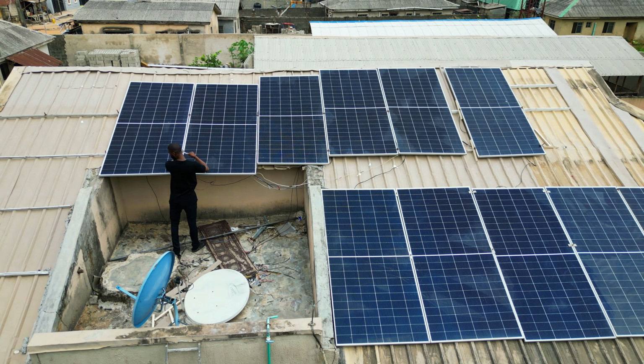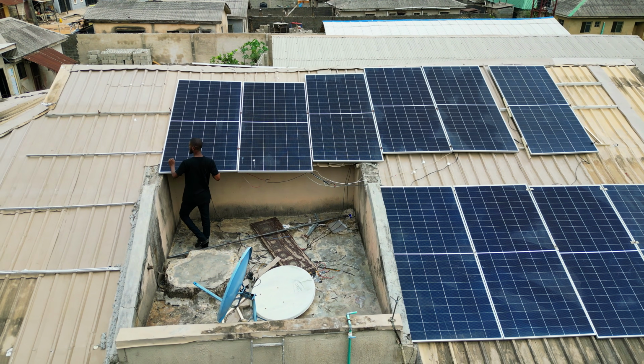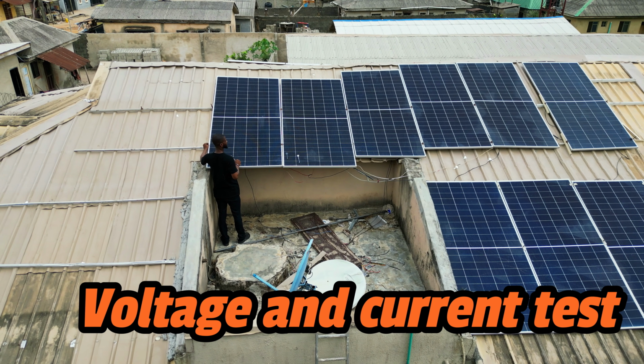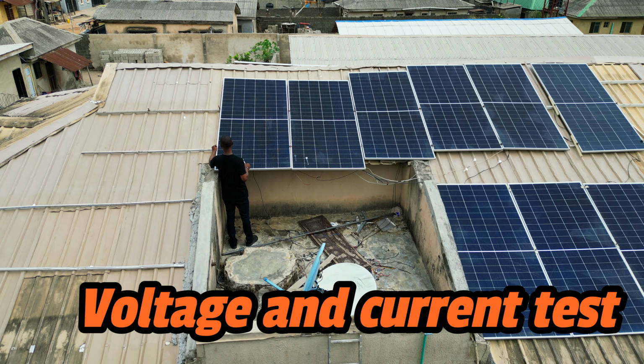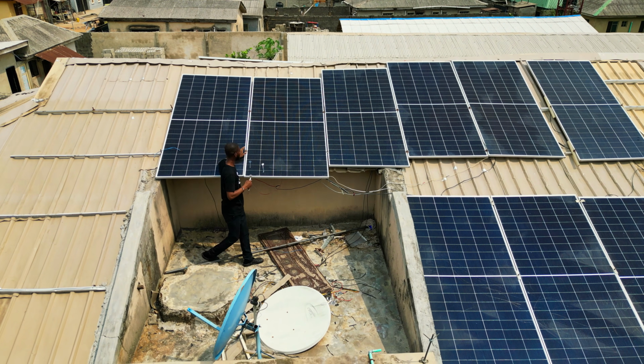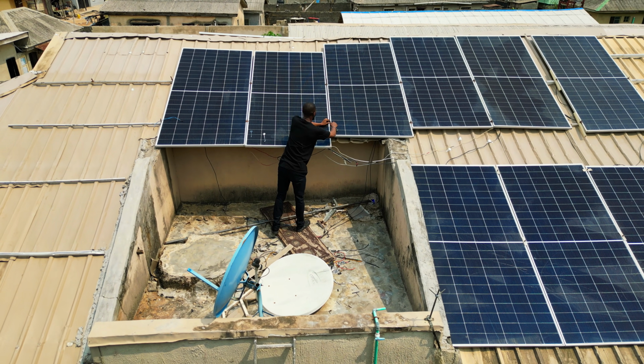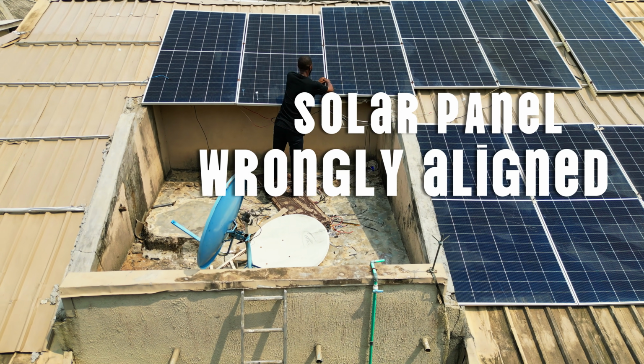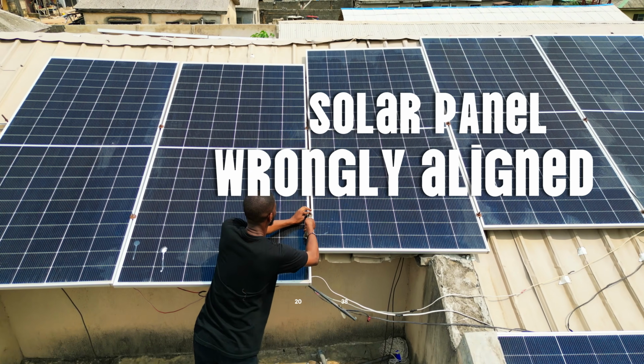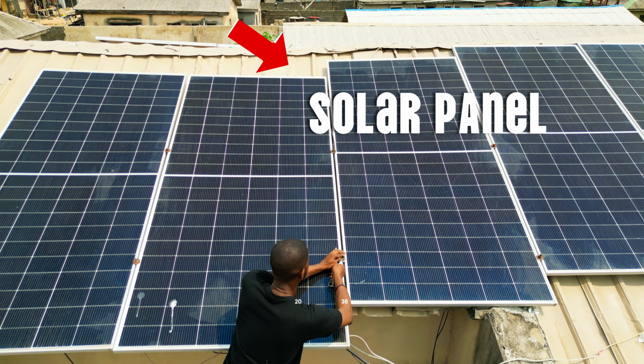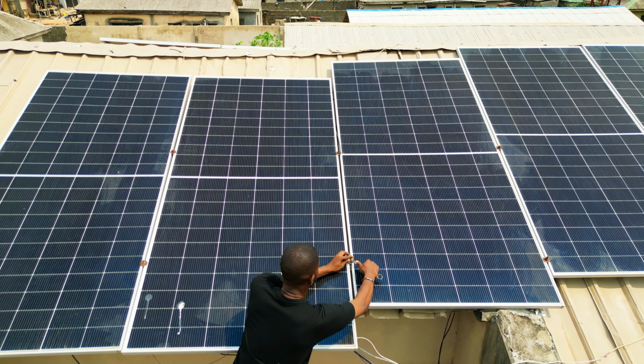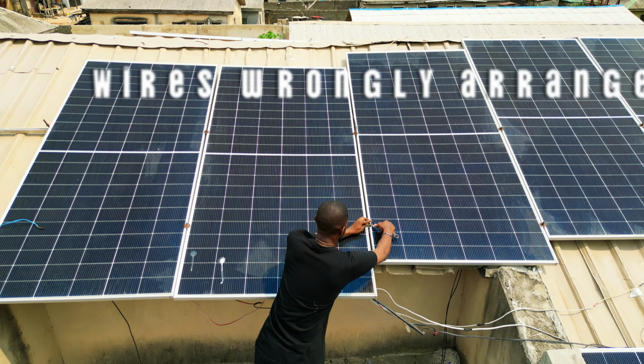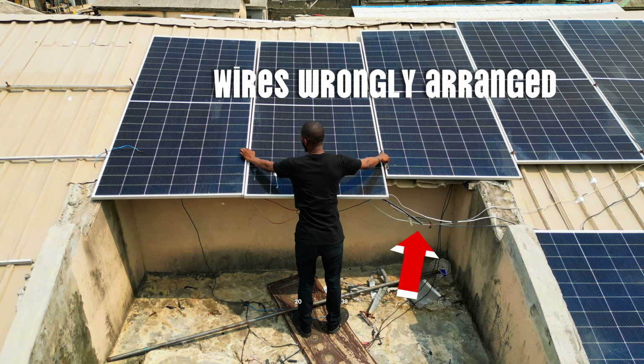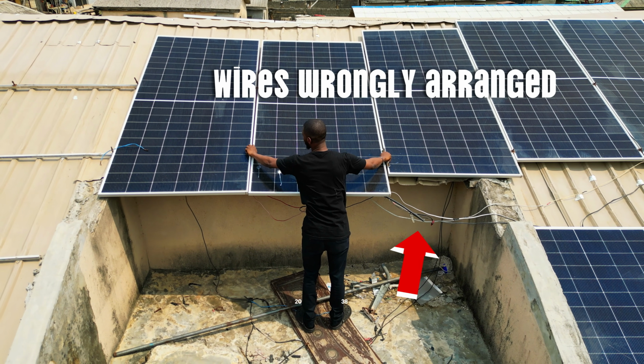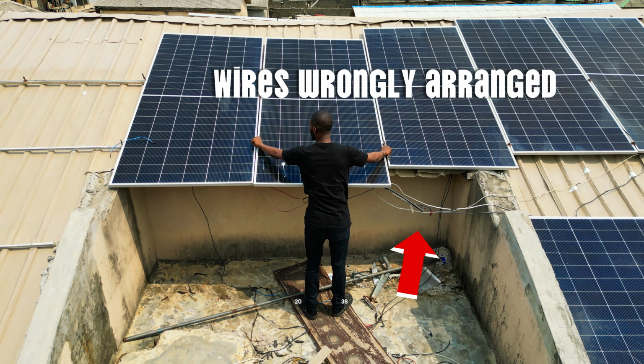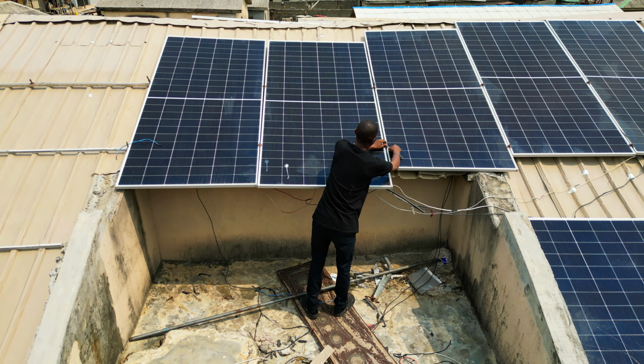He needs to take his time to check every single solar panel on that roof. That means every single one is coming down. We need to see what is going on, check if the wirings are connected properly, check for misalignment in the wirings and connections, check the configurations to know if it's properly done, and check if the wires are properly sized. Any undersized wires will definitely have to be changed. We just need to see what is going on. That's a whole lot to be doing for free.